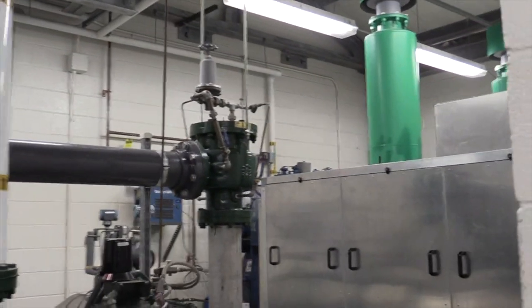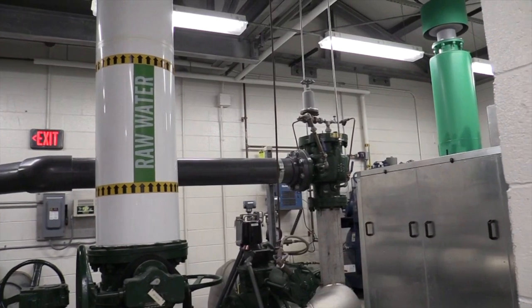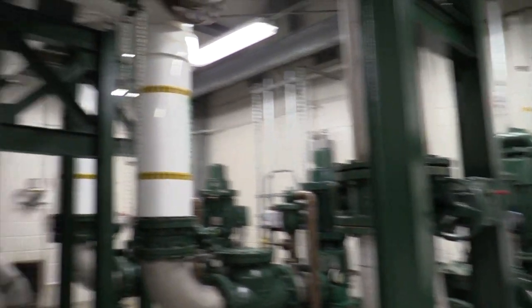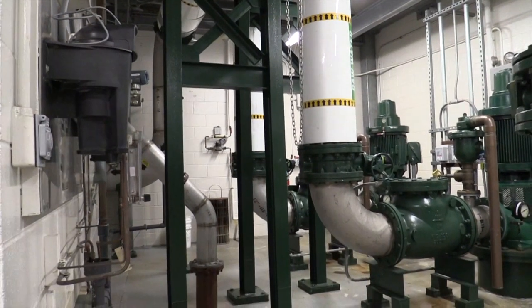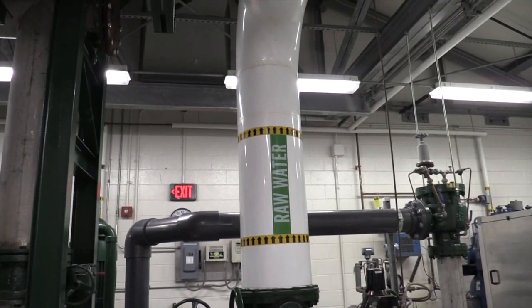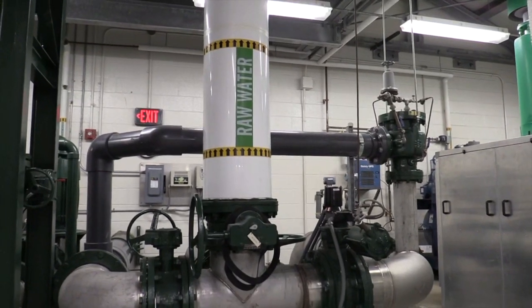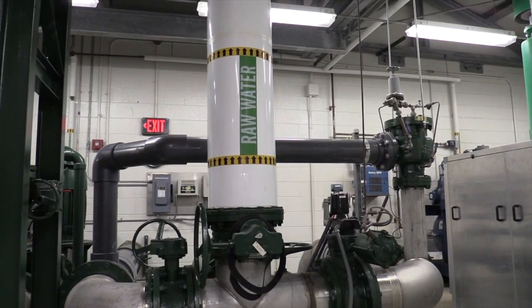The process all starts in our raw water room. We have two available sources. We can use vertical turbine pumps to lift water out of Reservoir No. 3, or we can use a gravity line out of Reservoir No. 5. That's the source we use in the summertime. When the water in Reservoir No. 3 warms up, we switch to Reservoir No. 5. The water is much cooler, much higher quality, much deeper, and by running on a gravity line due to elevation, we see about a $3,000 a month savings in electricity. It gives everybody in town much better water during those hot summer months when we tend to have taste and odor complaints.